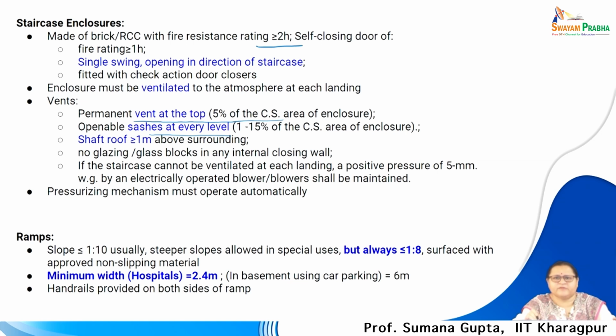If the staircase cannot be ventilated at each landing, a positive pressure of 5 millimeter, as we have already talked about in the pressurization mechanism earlier, should be integrated within the staircase enclosures. What is important is that because the buildings are quite high, people have to negotiate the height in case of a fire. The fire stair and all other staircases should be proof from smoke infiltration and fire, and safe in their integrity. It should be minimum 2-hour fire rated.